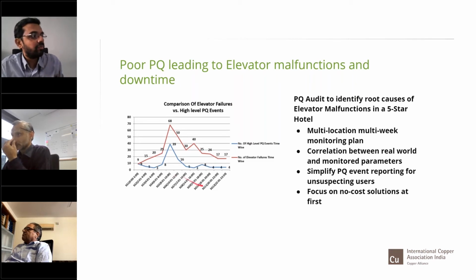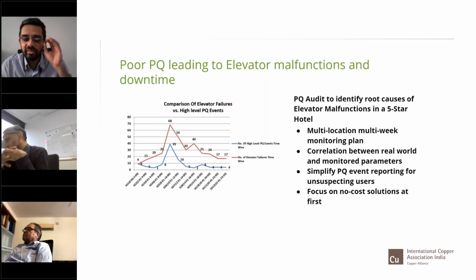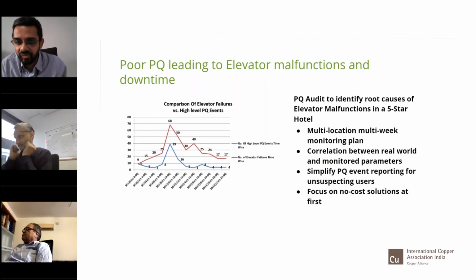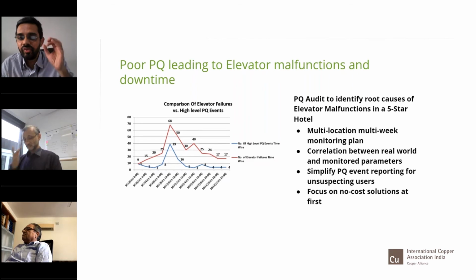The simple conclusion from this is that the number of elevator failure events had a very high correlation with power quality events occurring across the facility, and this is normalized over a 24-hour duration. And the simple output of this was that voltage sags were the cause of these elevator failures. A simple transformer tap change reduced 80% of these failures from there on. It was a free solution. They had to do nothing for it, but that's something they lived with for 4 years, and that's criminal in my opinion.